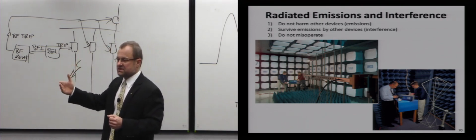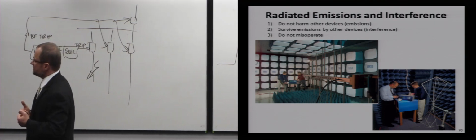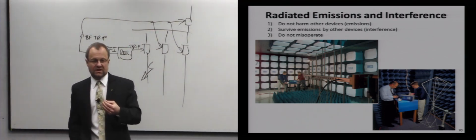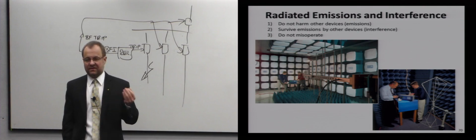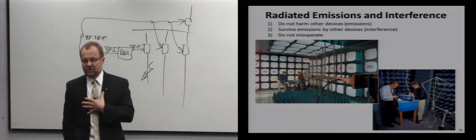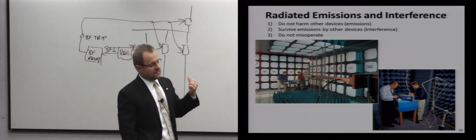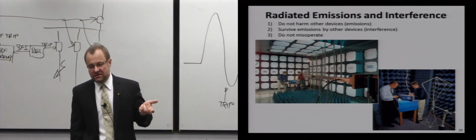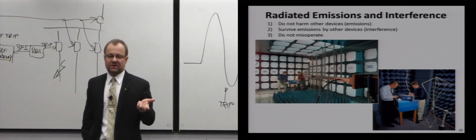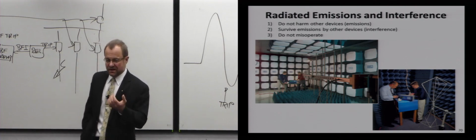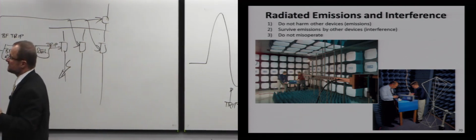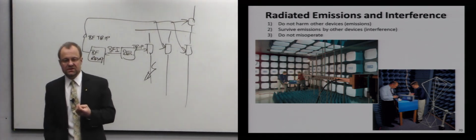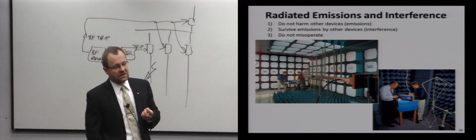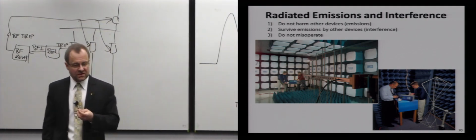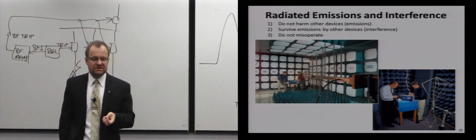Then we design relays to withstand that environment, but also those relays shouldn't emit too much noise because that affects other things sitting nearby. So I cannot do anything I want because, 10 inches away from my chassis, there could be some other relay or some other meter, and I cannot harm it to the point of rebooting it every 5 seconds, right? So I have to limit my emissions, and believe it or not, that becomes a problem because you are clocking so many things so fast, you are driving so many Ethernet ports and other communications ports that you become a noisy device.